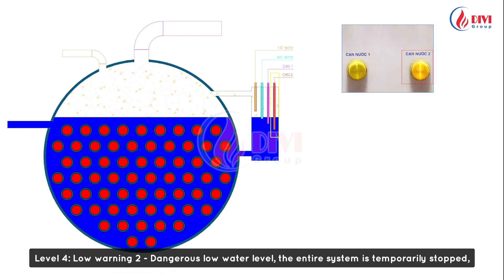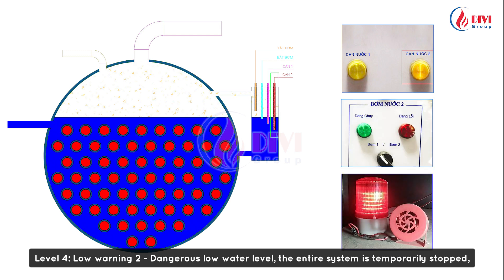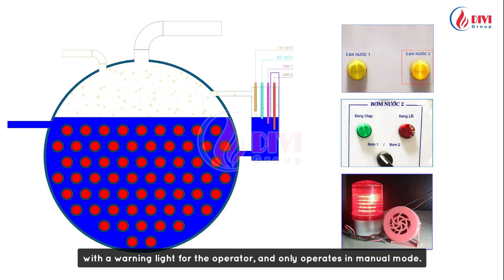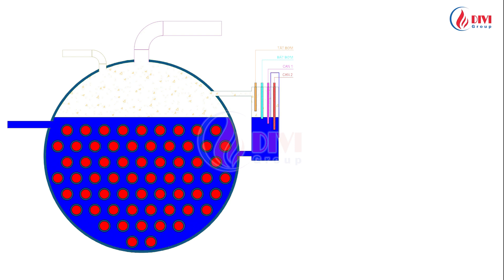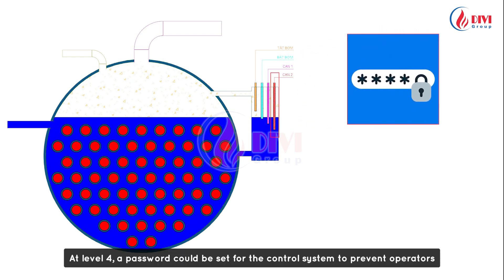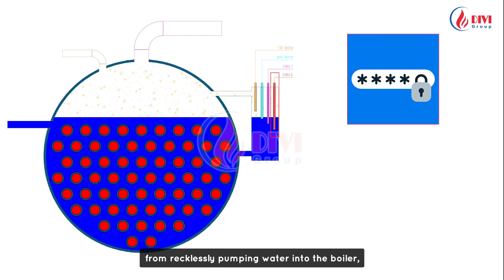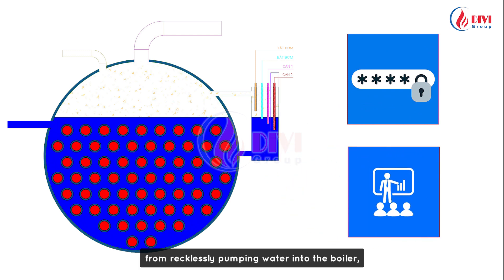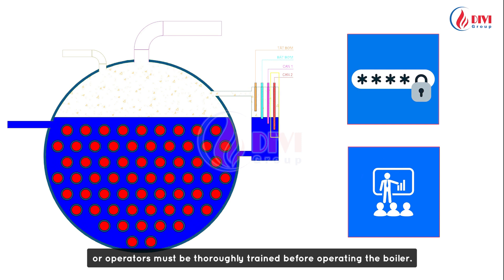Level 4 (low warning 2) — dangerous low water level: the entire system is temporarily stopped with a warning light for the operator, and only operates in manual mode. At level 4, a password could be set for the control system to prevent operators from recklessly pumping water into the boiler, or operators must be thoroughly trained before operating the boiler.